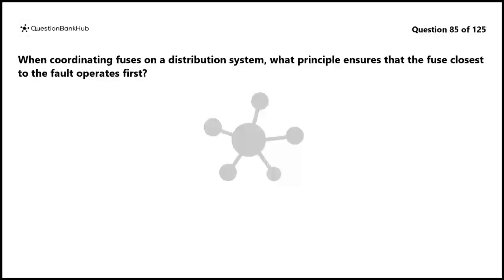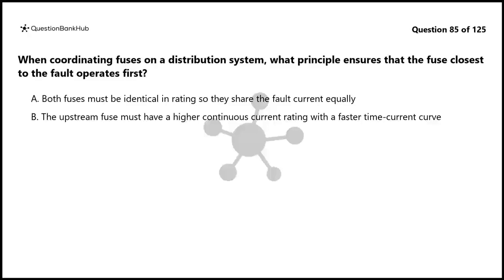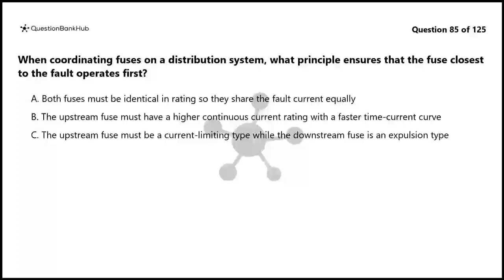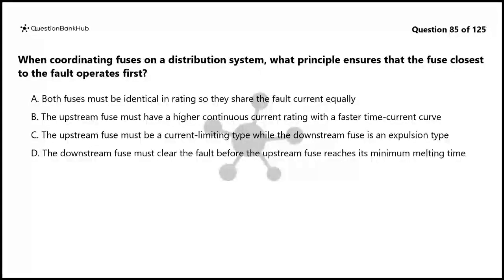Question 85. When coordinating fuses on a distribution system, what principle ensures that the fuse closest to the fault operates first? A. Both fuses must be identical in rating so they share the fault current equally. B. The upstream fuse must have a higher continuous current rating with a faster time current curve. C. The upstream fuse must be a current limiting type while the downstream fuse is an expulsion type. D. The downstream fuse must clear the fault before the upstream fuse reaches its minimum melting time.